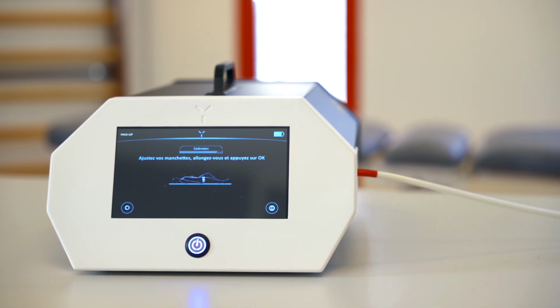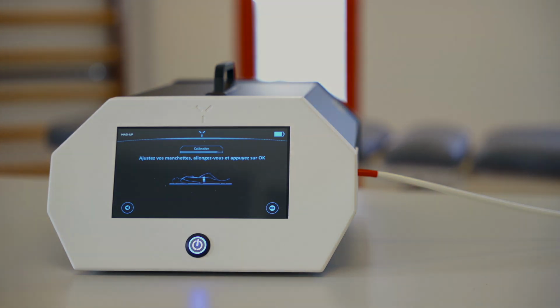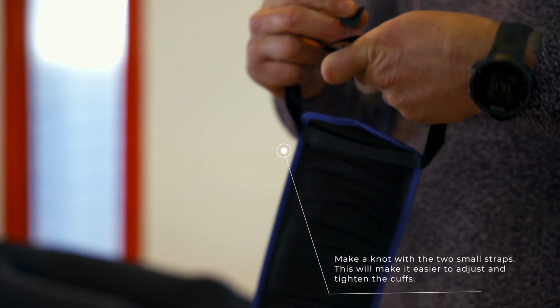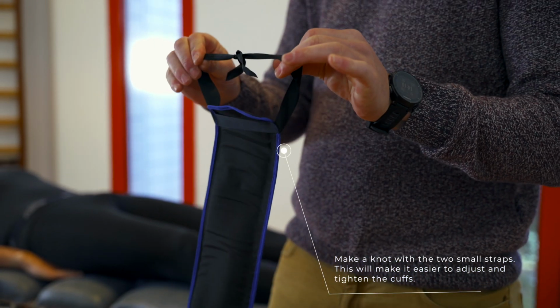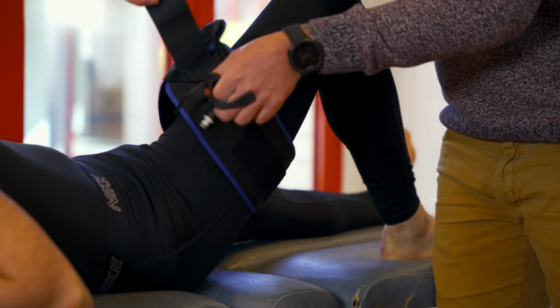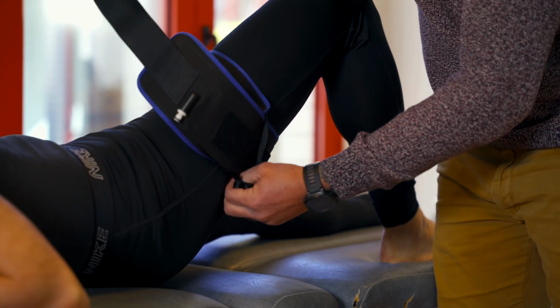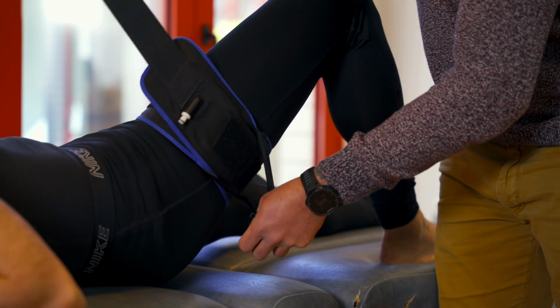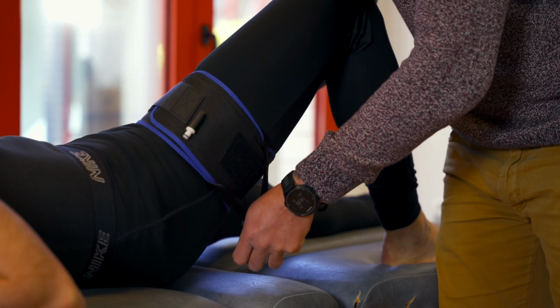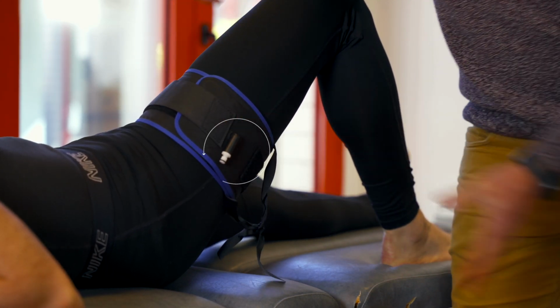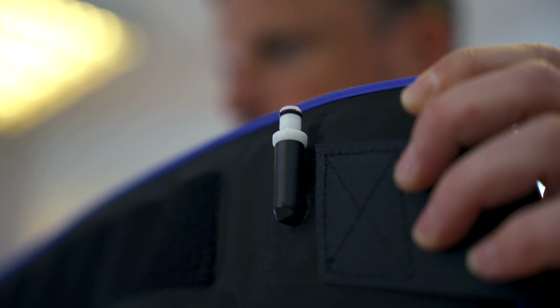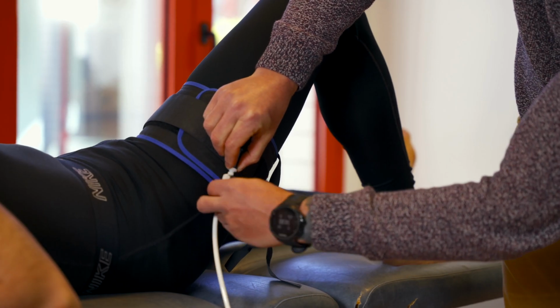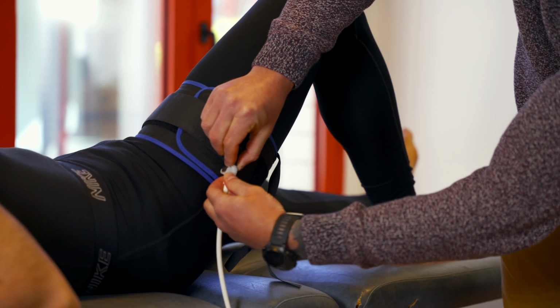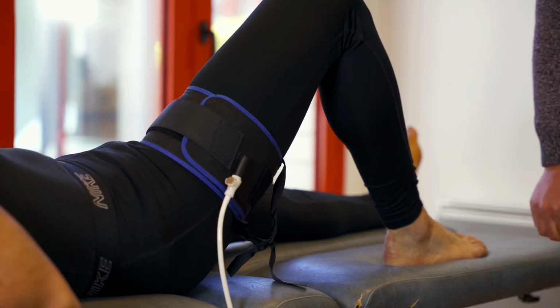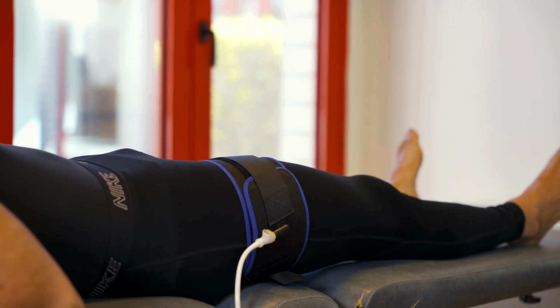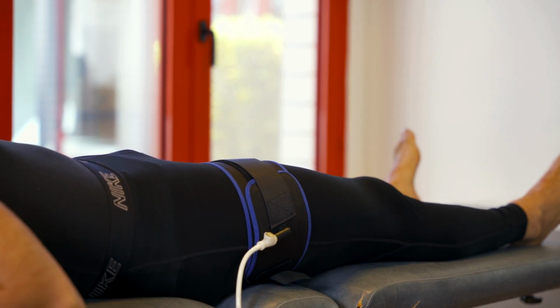You can now place the cuff over the limb or limbs you want to work on. Position the cuff firmly, making sure it is adjusted to the root of the limb. The connectors must be placed on the outside of the limb and facing upwards. As a safety precaution, remember to leave enough tube length for the cuff connectors when in use. The calibration phase can now be initiated.